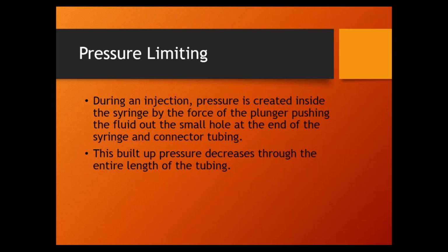Whenever you're filling the syringe, you're always supposed to fill with the head up, and then when you inject, you're always supposed to have the head down. Now, with older injector models, you're supposed to do that, but they don't care. If you want to shoot this thing pointed straight up in the air, it would let you do it. The newer contrast injectors, and this is one of them, won't let you do that. It makes the operator fill the syringe up, and makes them move the plunger forward 5 milliliters to purge the air out of it. Then, as one last resort, it won't shoot unless the injector head is pointed straight down.